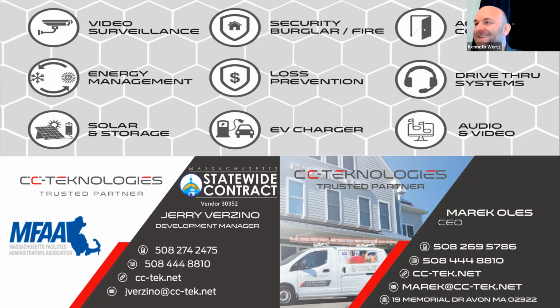I hate standalone systems. I'll make that statement. So I mentioned earlier, we do Dunkin' Donuts as one of our biggest customers. We installed 500 locations where, on the energy side of things, we gave them refrigeration control. So we control the defrost cycle. We monitor the temperature of the refrigeration. We monitor the energy of the refrigeration. We control and manage the temperatures for the HVAC. We monitor the temperatures coming out of the supply duct. We monitor the energy of that HVAC. We actually control their lighting with the astronomical clock, so you never have to have those dog legs pop out and change them. And we also control and monitor their appliances.